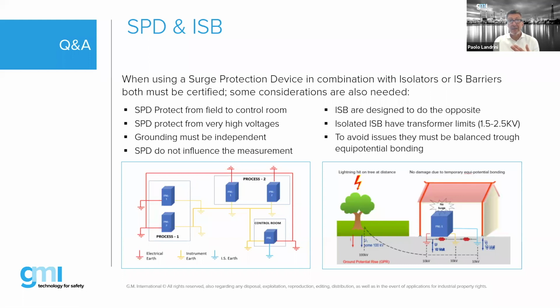Inherently, the barrier is not designed to do surge protection, but it can act as a surge protector within the limit of the barrier. So the barrier is typically at 1.5, 2.5 kilovolts of isolation. If you have a surge coming back from the field up to that level, the barrier will protect what is behind that, so the PLC. But for sure, the barrier will be destroyed. It cannot be protected, whereas an SPD can.